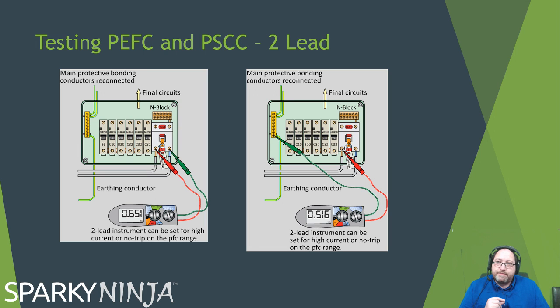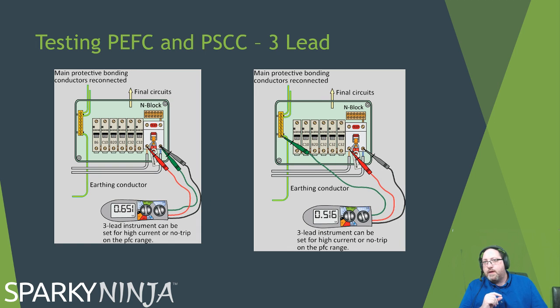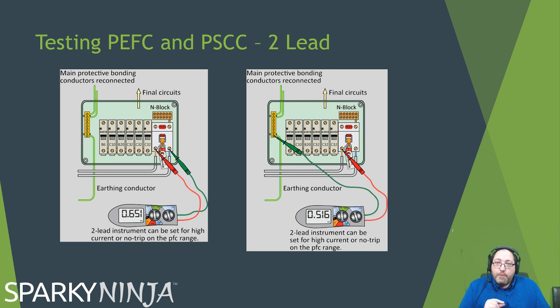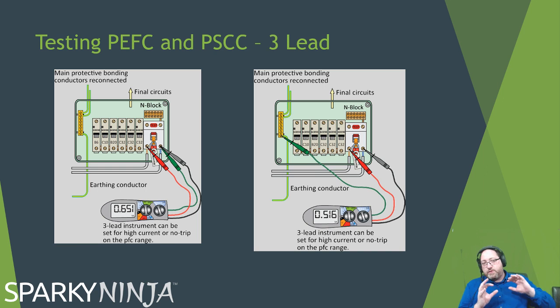If you have 3 leads, it can be a bit confusing. The earth measurement isn't as bad if you look on the right. All we've done between this one and this one is taken that 3rd lead and put it on neutral. Another polarity thing. That's fine. Great. Look at the left though. When we do the prospective short circuit current between line and neutral, we don't want to go on an earth because that's an alternative resistive path. It's going to be a lowered resistive path. It's going to give us an inaccurate reading. So we double that up. That can be a bit awkward depending on your test lead configuration. You may have a piggyback system. You may be trying to crock one lead to the other.